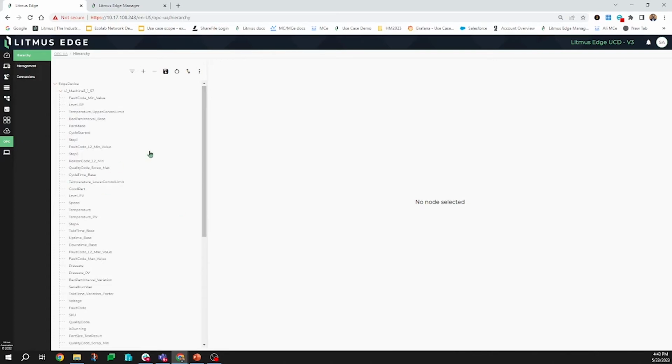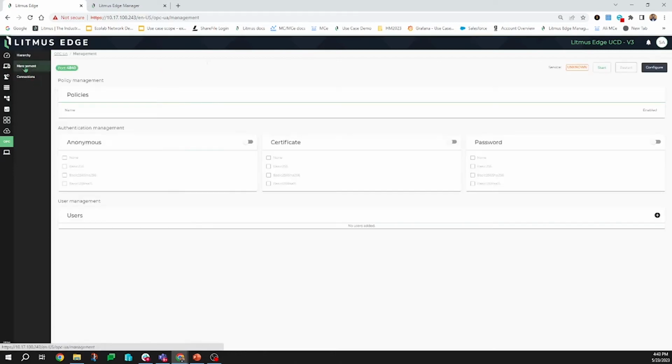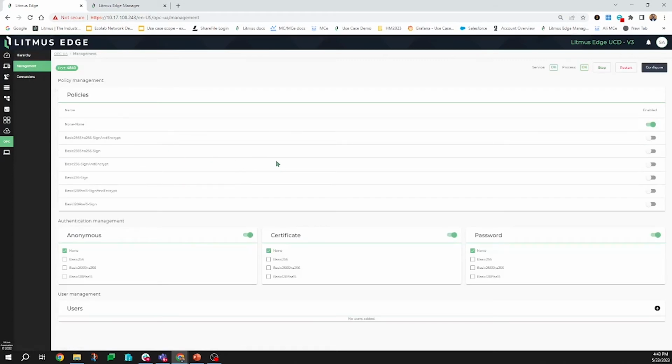You can also create your own custom OPC UA server by adding analyzed data to it. So for instance, if you calculated OEE at the edge, you can create a tag called OEE and expose that as OPC UA to be used by other systems such as the SCADA and actually do the calculations here locally at the edge. The connections to the OPC UA server include all the standard security policies that are available, so require or not require certificates, usernames, or passwords. And you can configure the port and IP address of the OPC UA server.